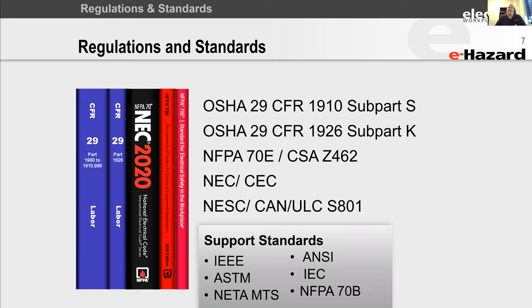And if there's reason to, we'll apply temporary protective grounds to protect the employee. That's how 70E's priority is for meeting the OSHA standard. We're going to consider that in 70E as being hazard elimination. If we've taken the hazard out of the equation, it becomes very easy for the employee to work on that equipment and not get hurt, and this human performance stuff becomes a little bit less of an issue.